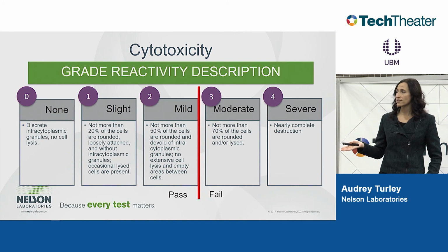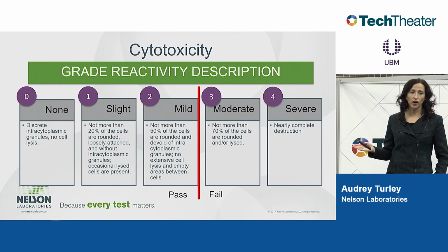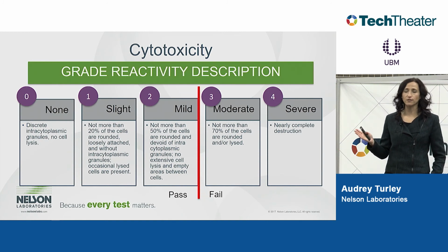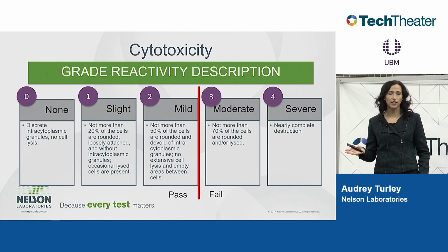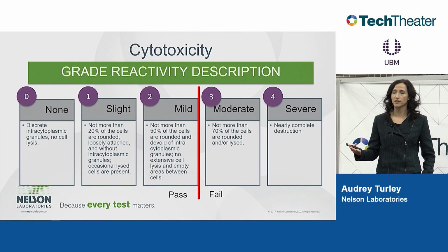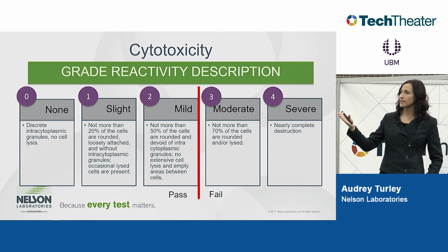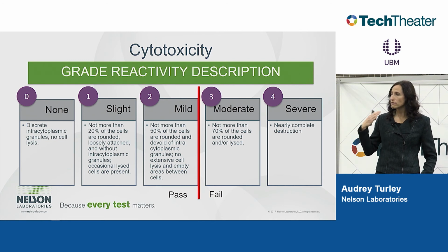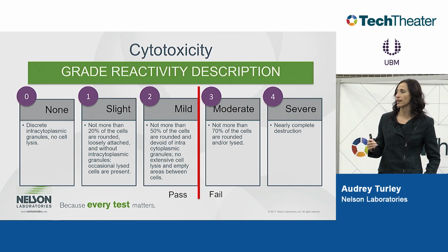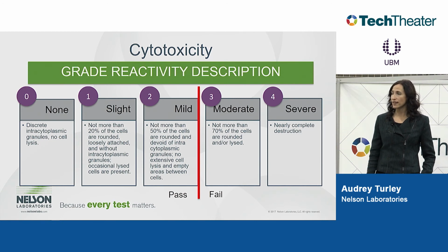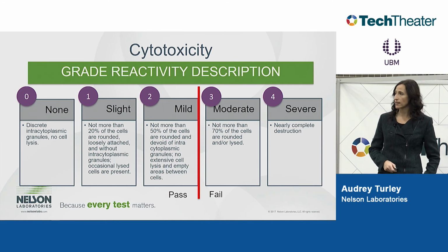So for cytotoxicity, on the scale of 0 to 4, this is a subjective test. So this is based on an analyst's interpretation of what they look through the microscope and see. So they're just basing this score off of their interpretation of the view that they can see of the cells. And if we have a 2 or lower, that's considered passing. If you're a 3 or above, then you're failing the cytotoxicity test.